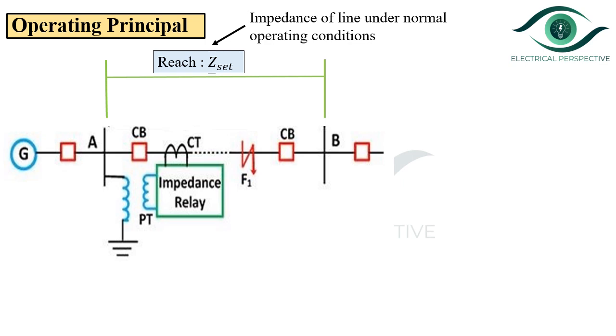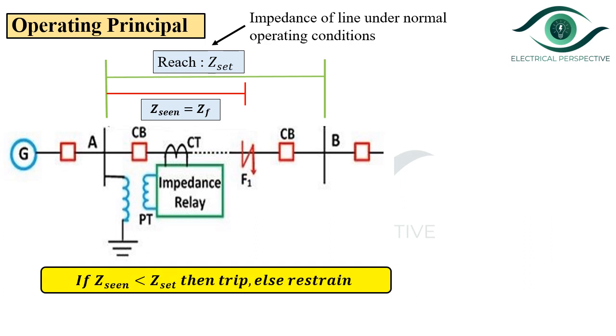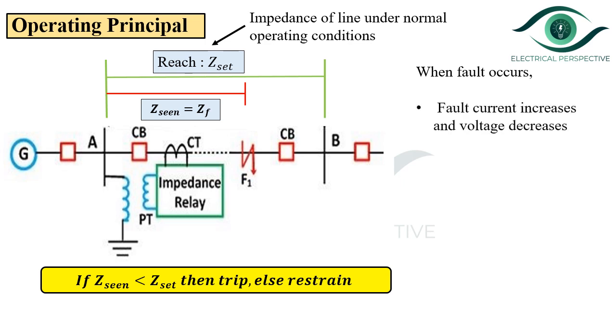Assume that a fault occurs at point F1. As this point is within the zone, this fault is called an internal fault. The relay will compute the impedance as seen from its location and compare it with the set value to take the trip decision. We know that if Z-seen is less than Z-set, the relay will trip; otherwise it will restrain. When the fault occurs, the fault current increases and the voltage decreases. Since Z-seen equals V by I, as current increases, Z-seen will decrease. As Z-seen is less than Z-set, the relay will trip. So for an internal fault, the relay will operate.